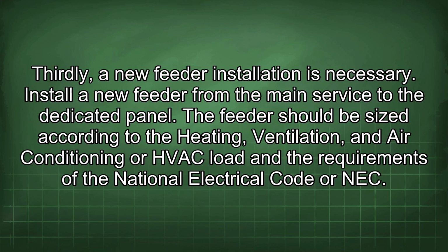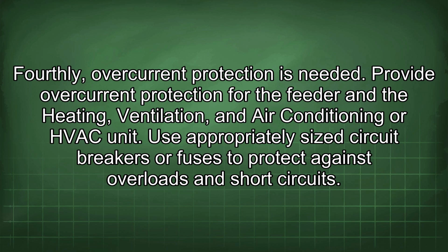Thirdly, a new feeder installation is necessary. Install a new feeder from the main service to the dedicated panel. The feeder should be sized according to the heating, ventilation, and air conditioning, or HVAC, load and the requirements of the National Electrical Code, or NEC. Fourthly, overcurrent protection is needed. Provide overcurrent protection for the feeder and the heating, ventilation, and air conditioning, or HVAC, unit. Use appropriately sized circuit breakers or fuses to protect against overloads and short circuits.